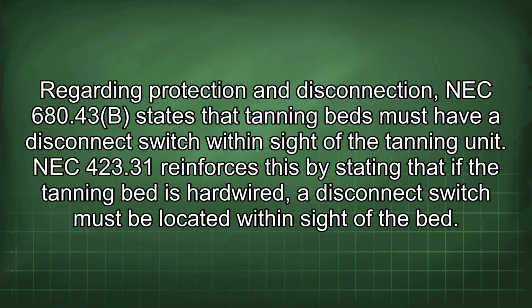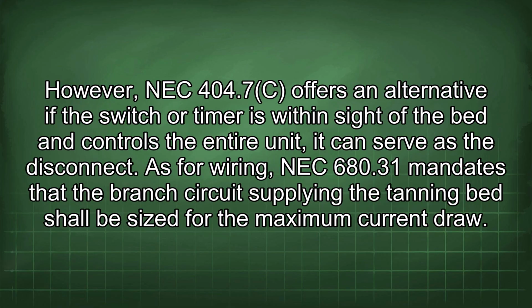Regarding protection and disconnection, NEC 680.43b states that tanning beds must have a disconnect switch within sight of the tanning unit. NEC 423.31 reinforces this by stating that if the tanning bed is hardwired, a disconnect switch must be located within sight of the bed. However, NEC 404.7c offers an alternative.